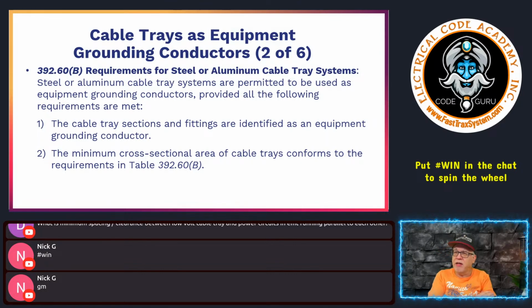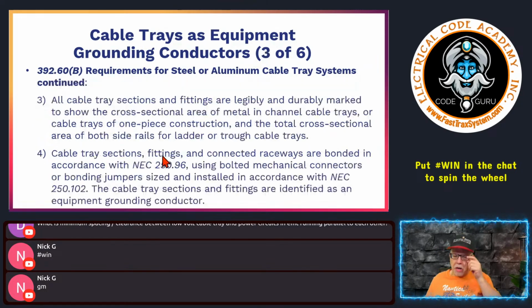But again, if you have 600 volt rated cables or conductors in there, and you're going to be putting in lower voltage, just like when you go into a box, you're going to have some type of separator in there. If you're low voltage, for like your data communication and things like that, you're going to have the ability to have a separation. Okay. All right, let's go on.